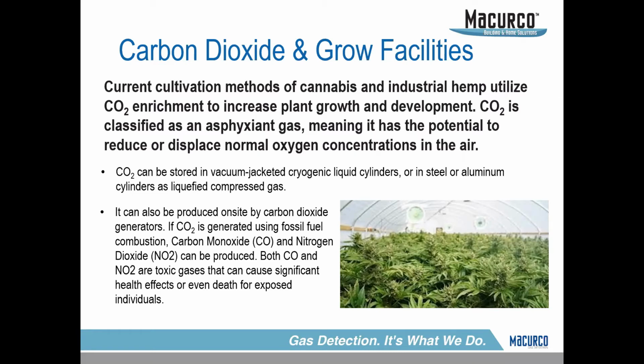If CO2 is being generated, if it's not just brought in, it's being done by fossil fuel combustion. So carbon monoxide and nitrogen dioxide can actually be produced because of this - CO and NO2 are a big factor as well. So it just depends on how they're bringing in their CO2. If they're just buying it from a supplier and it's sitting there being pumped into a room, that's one thing. But if they're generating their own CO2, that's a whole other ballgame of detectors - now we need CO2, CO, and NO2. So there's a lot of opportunity here for multiple gases.